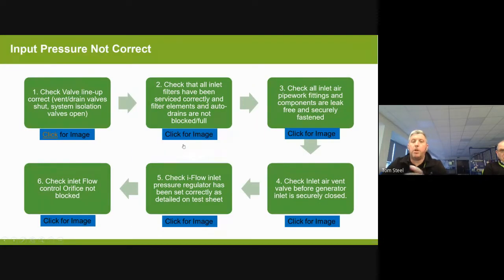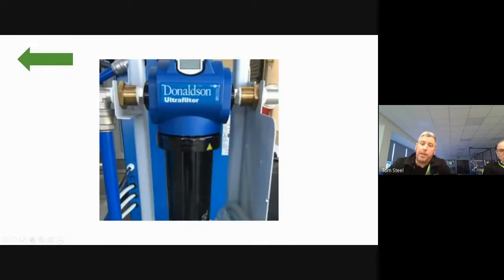We're also going to check that inlet filters have been serviced correctly, and that the filter elements and auto drains are not blocked or full. The auto drains are there to remove the moisture. Our filter element is here. At the bottom of this, there will be an auto drain. The auto drain is there to sense the level of moisture that's been trapped by the filter and then remove it to the condensate, which is going to the oil water separator. So we need to ensure that the filtration is not blocked and also that the auto drain is working.